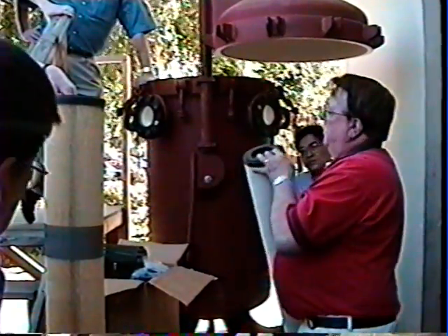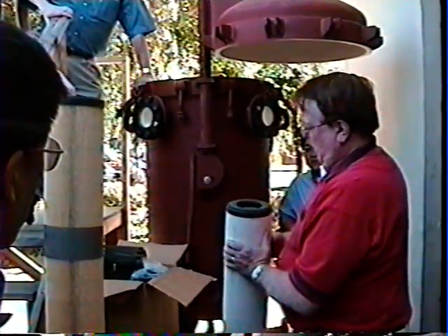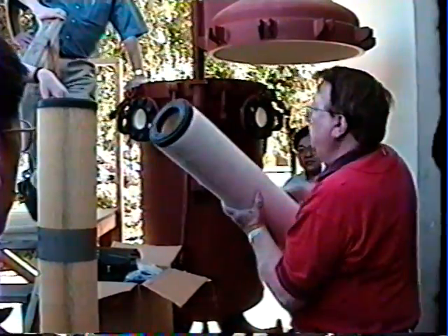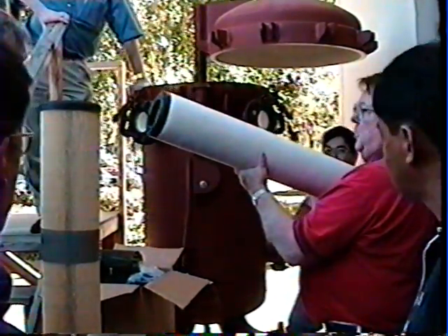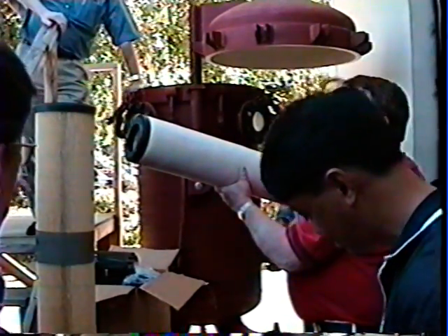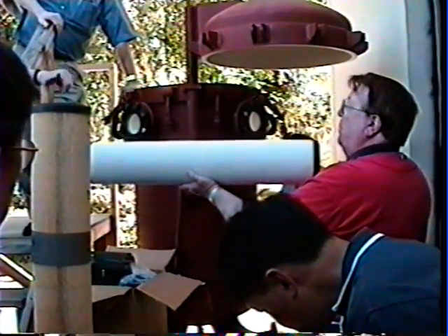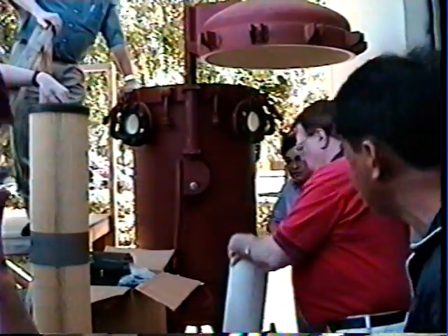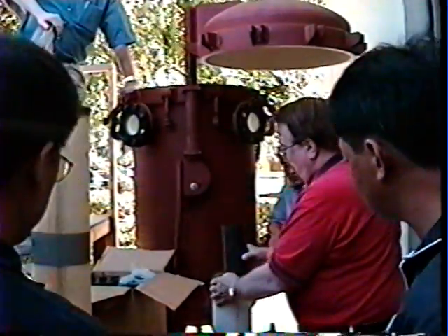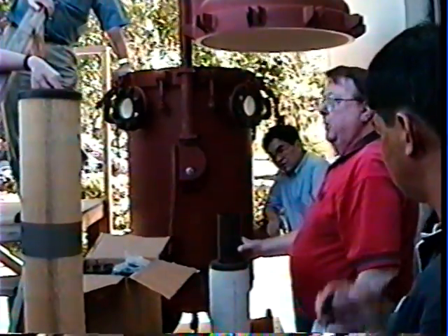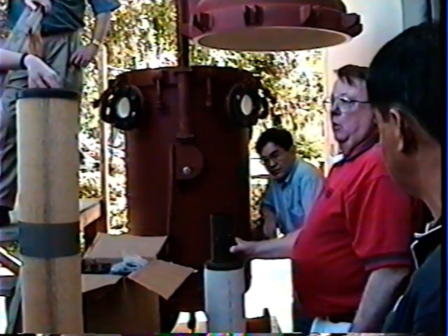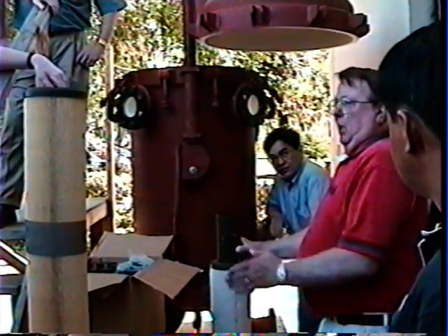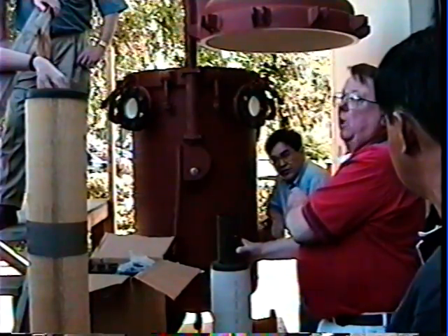Okay, let's check something here. Did we have a good seal here? How can we tell? You can see the ring from the spider. Now, where we get in trouble is if our marks from our spider are like this. And you can see it after the element's been in there a while. You will see the difference rather than this. And you'll know.